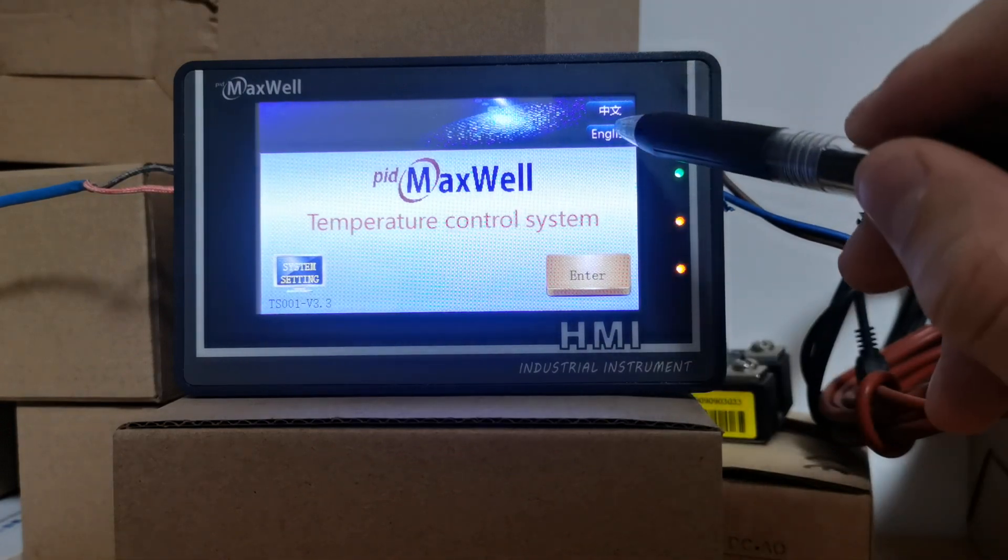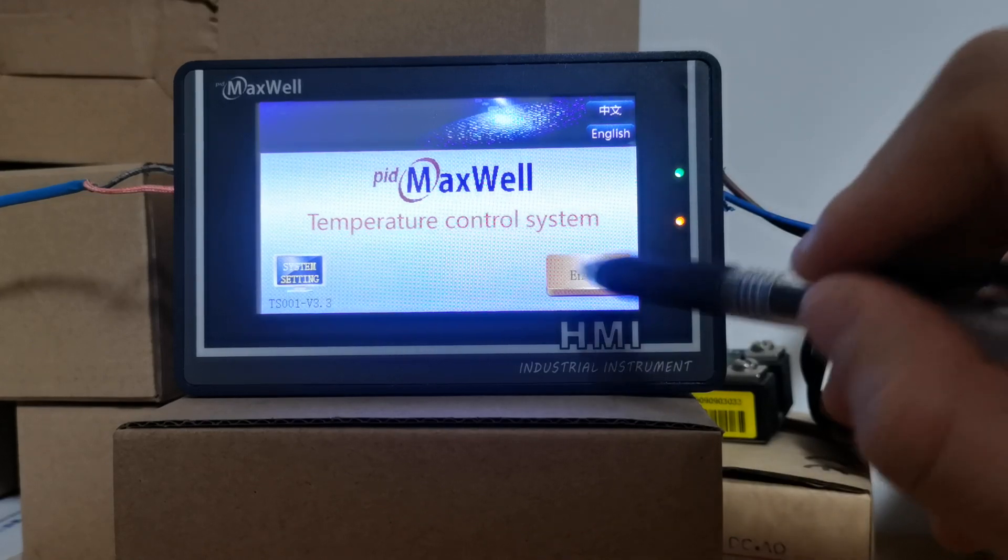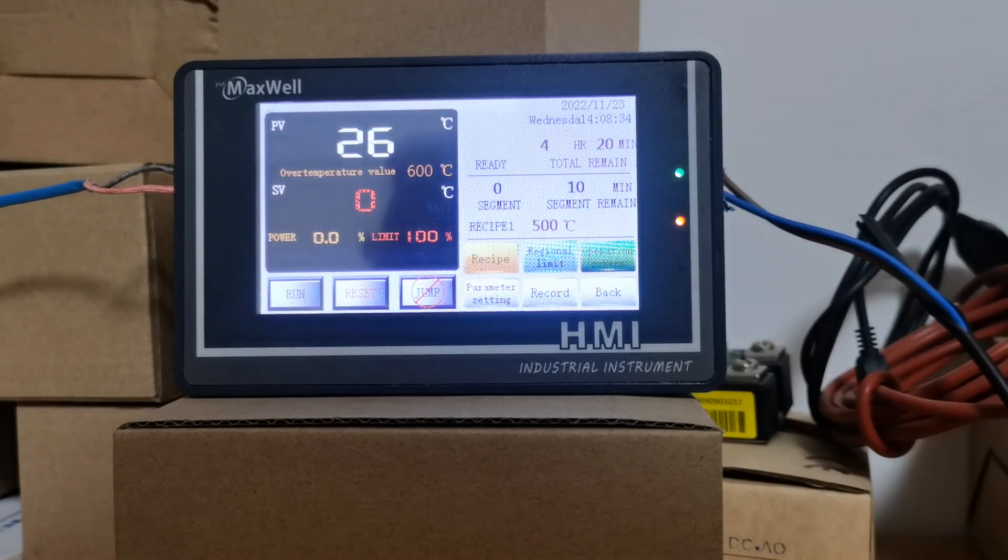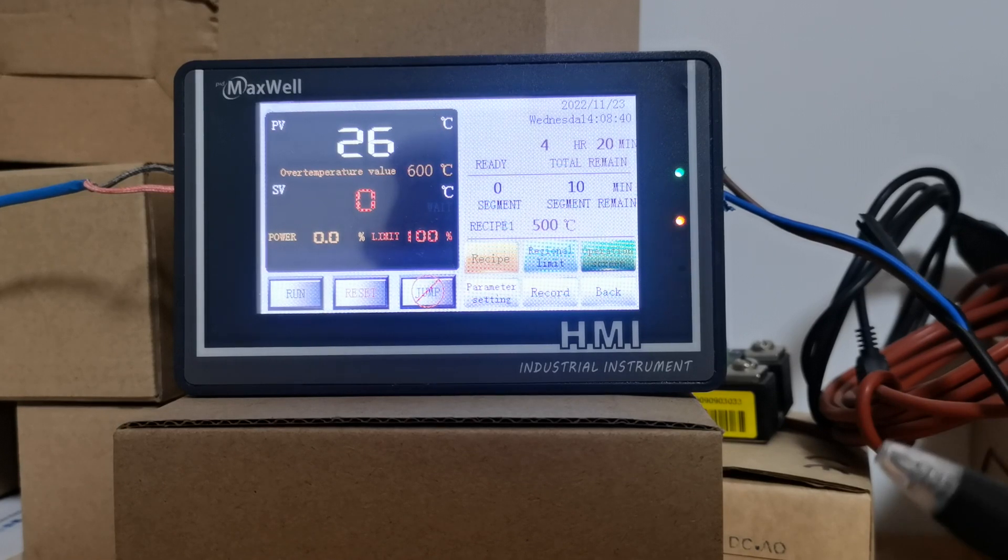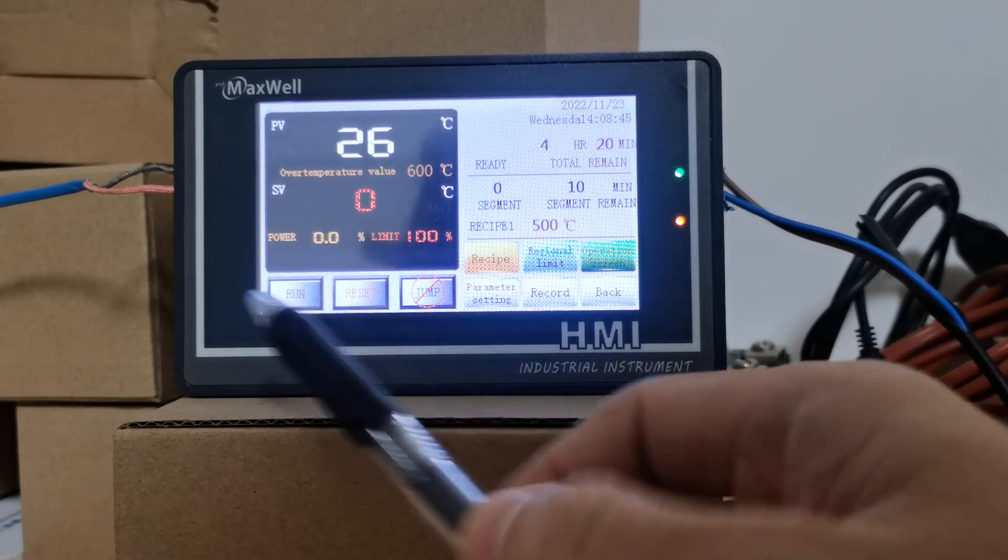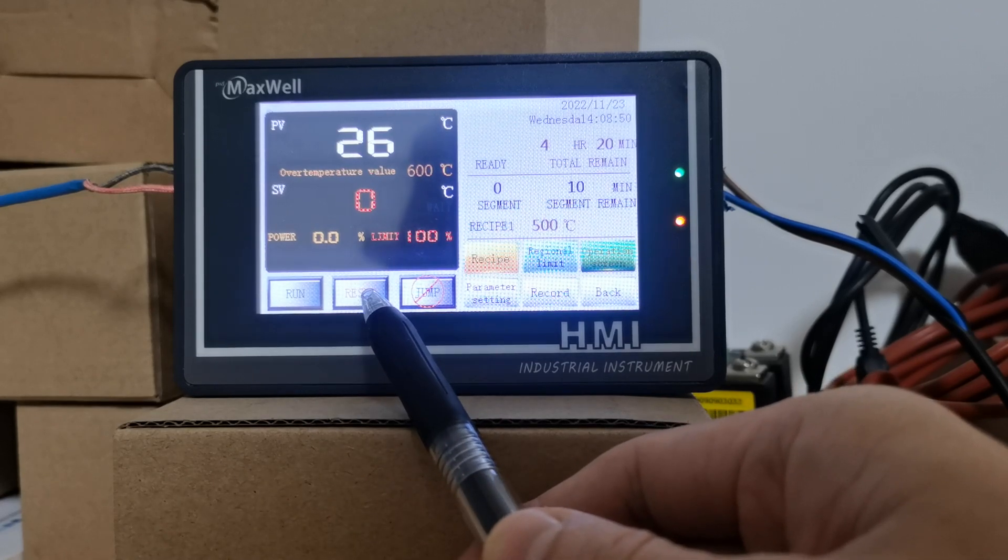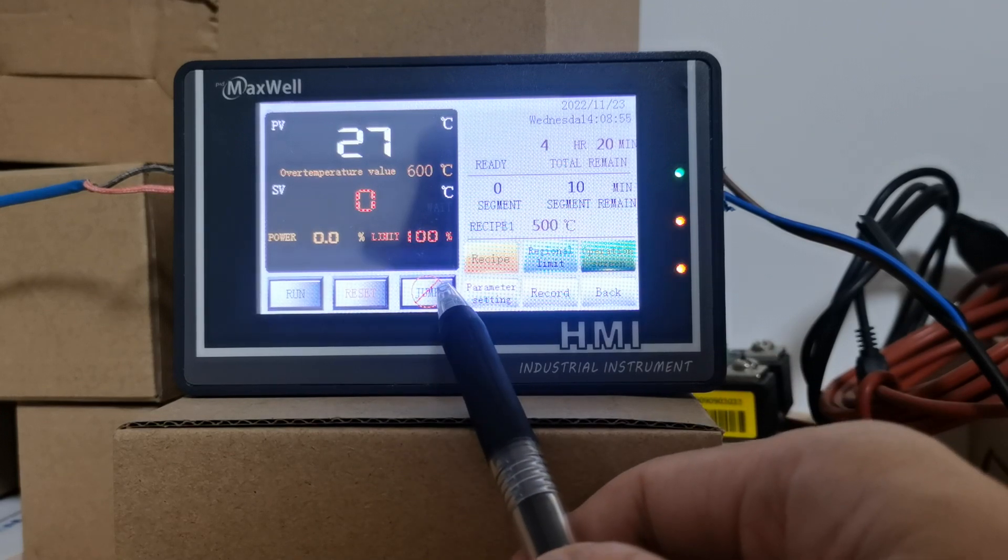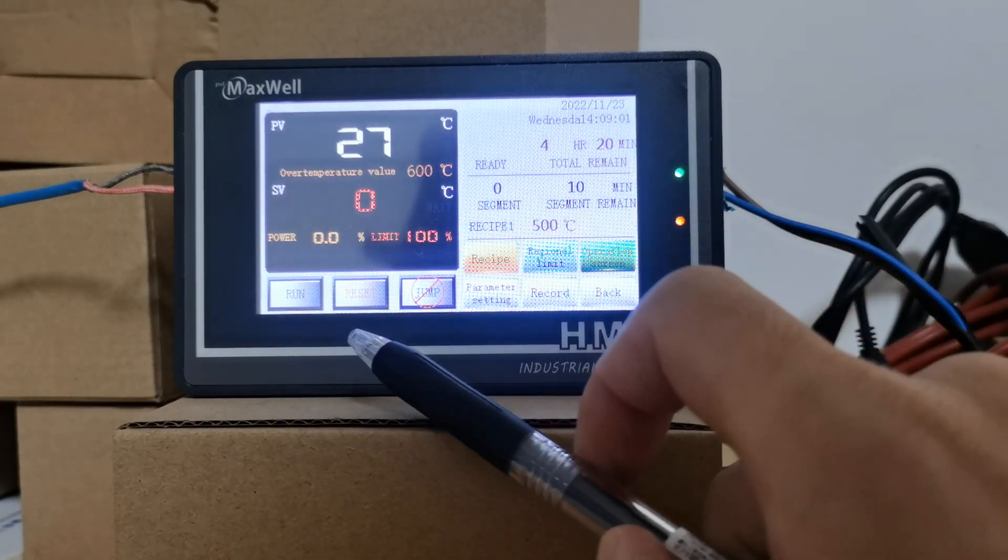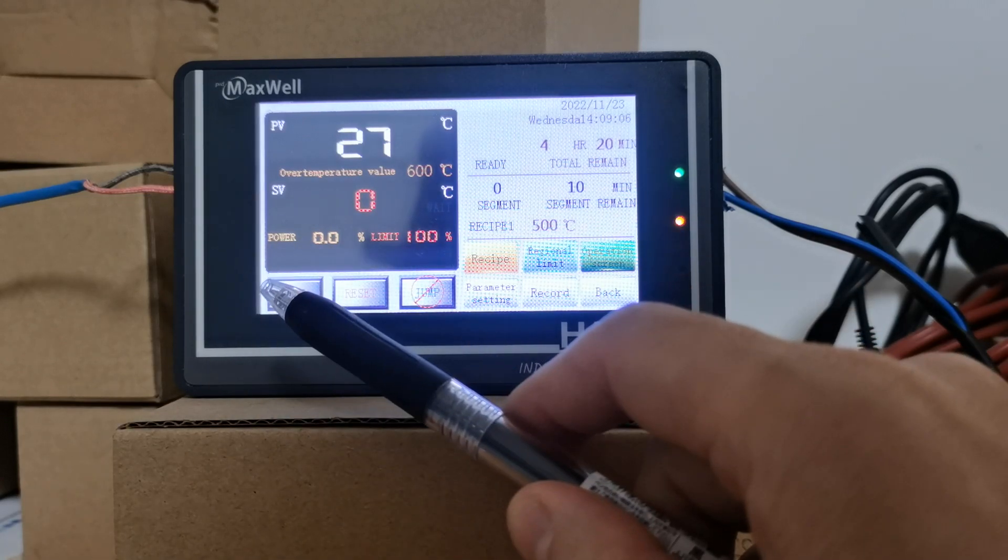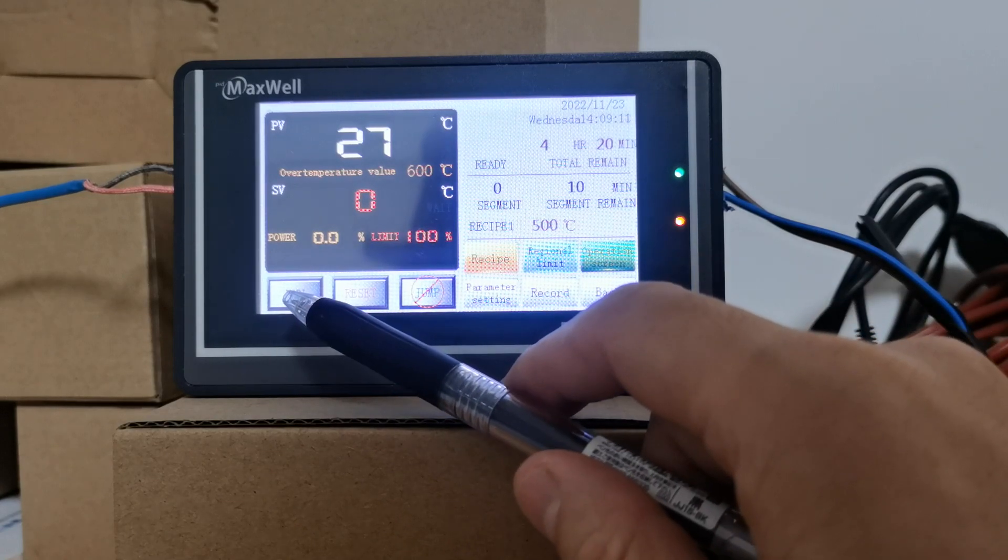Press the enter button. Now here's the main display screen. Run means you can run the program after you finish all the settings. Reset is where you can reset the program. For example, if the program is at segment number seven, you can press the reset button and the controller will go back to ready mode, and then you have to press run again to run the program.